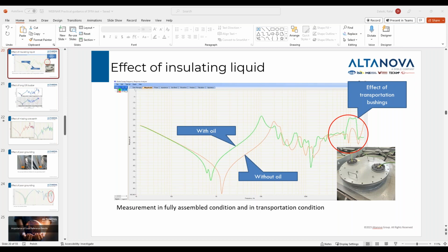But when they don't align very well, you can try to interpret them on the basis of these influencing factors, which I presented before, to see whether one of them could be the reason for what you are seeing, or if it's similar to something you saw before on another transformer of similar type maybe. So yes, it's going to be more difficult then, and it's the majority of the cases. But if you have a network of transformers, there are usually more transformers of similar type, and you can also schedule another transformer for testing, which would be similar.